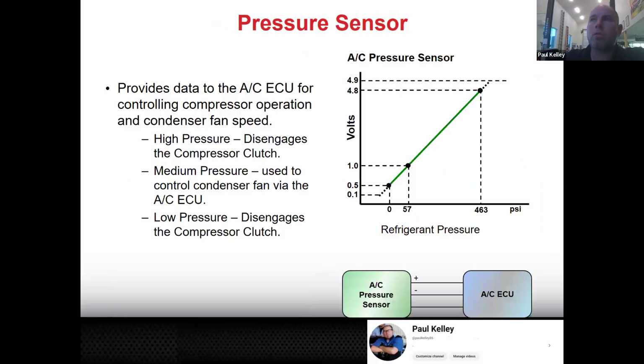It's pretty simple. For the pressure sensor, if you have 0.1 volts, that would be out of spec - you're going to get a code, the circuit's open or shorted to ground. But if you have 0.5 volts, that's about zero. If you have 1 volt, that's about 57 psi. If you have 4.8 volts, that's about 463, which is pretty high. If you have 4.9 volts, that's off the charts - that means it's either got an open ground or the signal is shorted to the 5-volt reference.